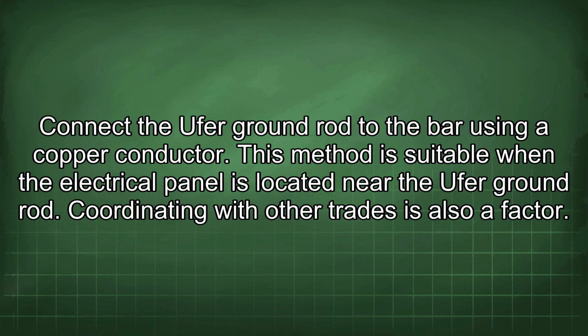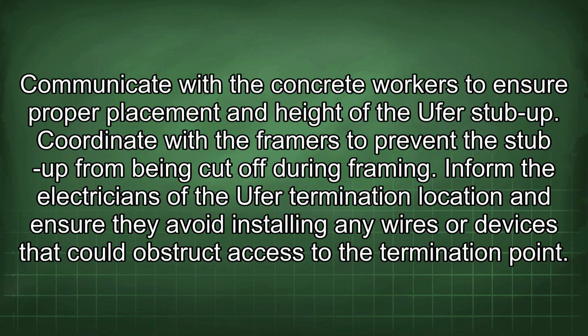Coordinating with other trades is also a factor. Communicate with the concrete workers to ensure proper placement and height of the Ufer stub-up. Coordinate with the framers to prevent the stub-up from being cut off during framing. Inform the electricians of the Ufer termination location and ensure they avoid installing any wires or devices that could obstruct access to the termination point.